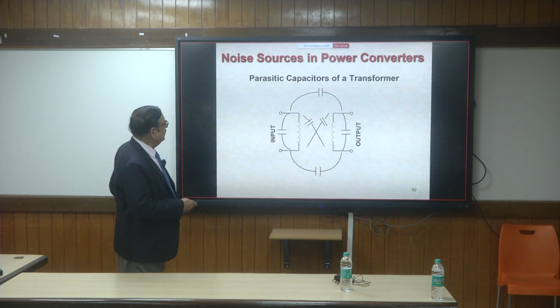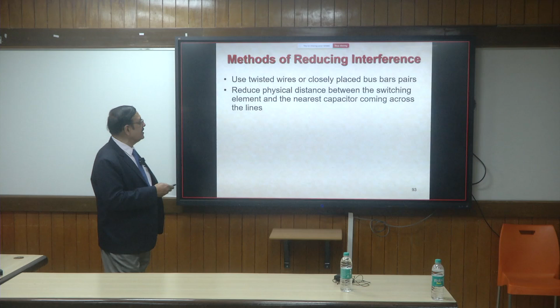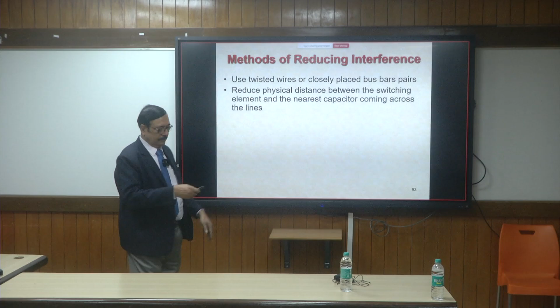You can't see it. Reducing interference: use twisted wires or closely placed busbar pairs. They have to be very close to each other so that flux coupling is there. Reduce physical distance between the switching element and the nearest capacitor coming across the lines. Let's say you have a rectifier, you have an inverter, in between you have a DC bus, you have filter capacitors. The question is, where do you place it? Near the rectifier or near the inverter? If they are far away, best is, of course, to make them close to each other, but it's not possible all the time. So in that case, you have to split. Part of the bank will be on this side for the rectifier to cater to the ripples coming from the mains. Part of the bank will be on this side to cater to the ripples that are coming from the inverter.